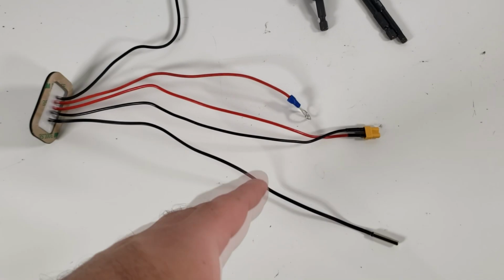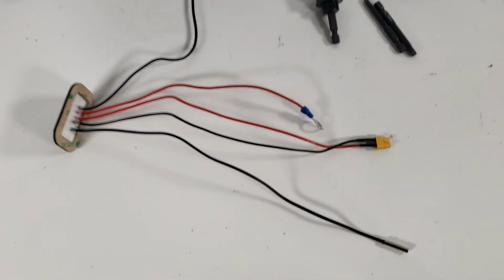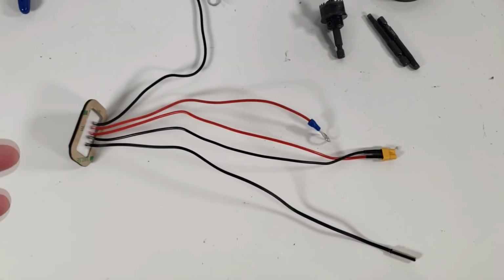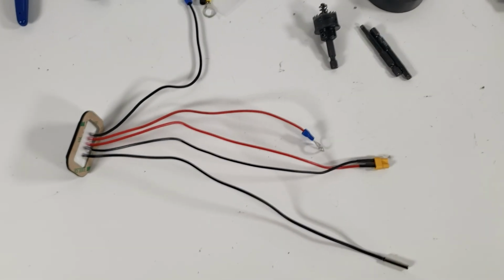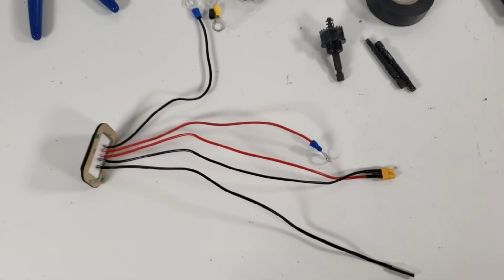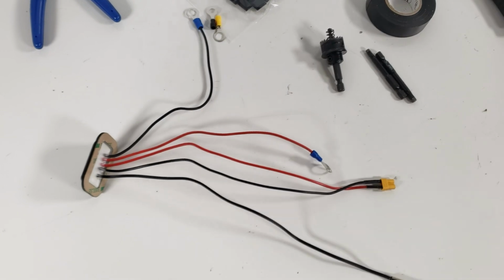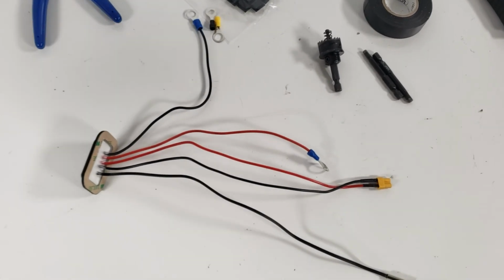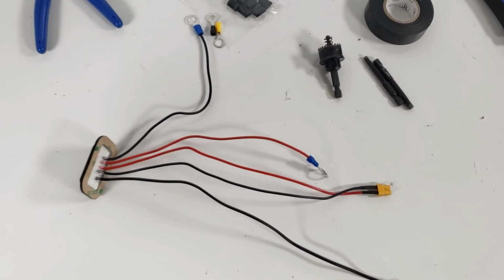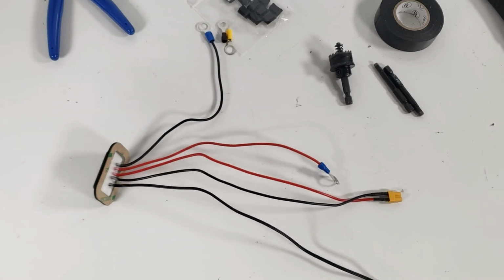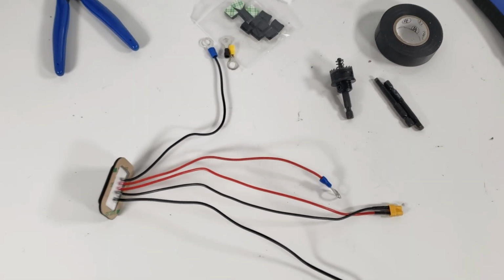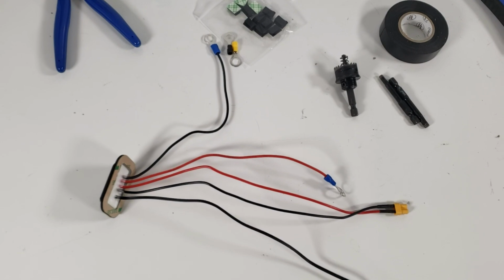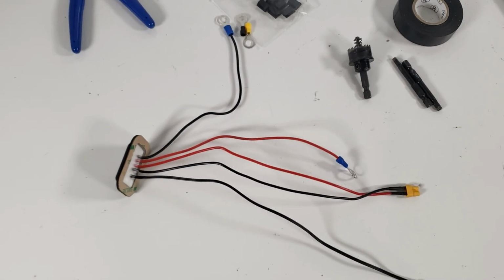This is needed because normally this is set up to be installed in a switch that does not have a heating port. But since we do have a heating port in the 200, we want to prepare the switch so it will still allow the standard switch auto failsafe for heating. So even if the switch is off, the BMS will still turn the heating pads on at low temperature for low temperature charging.